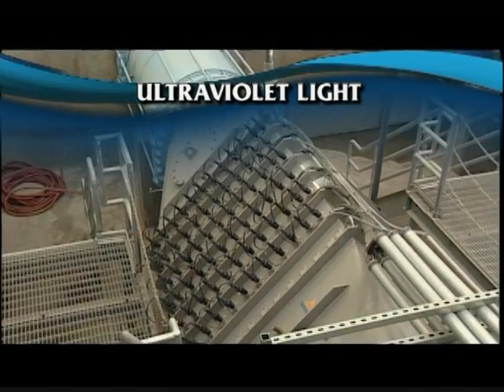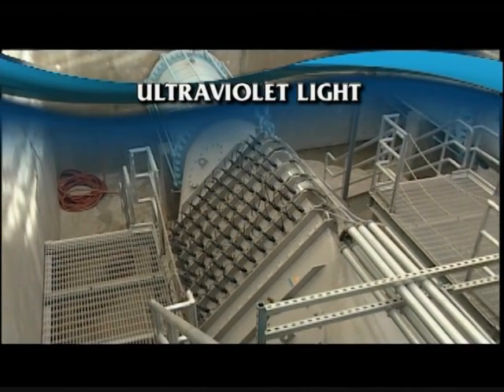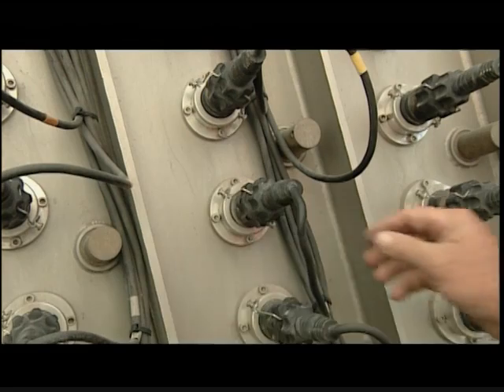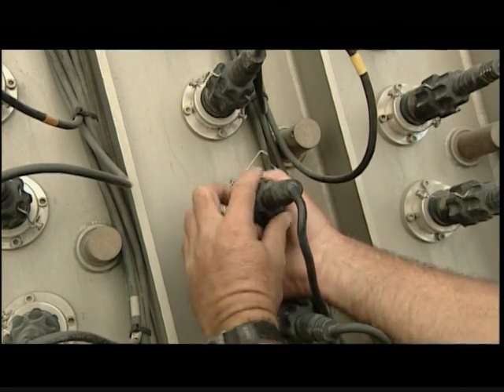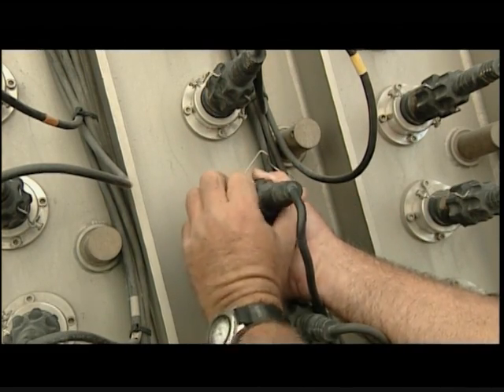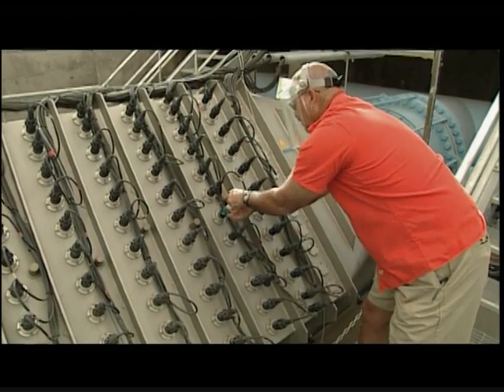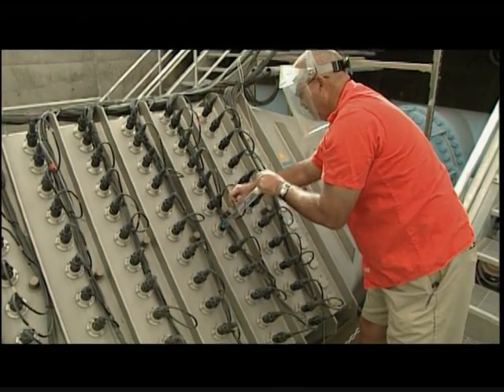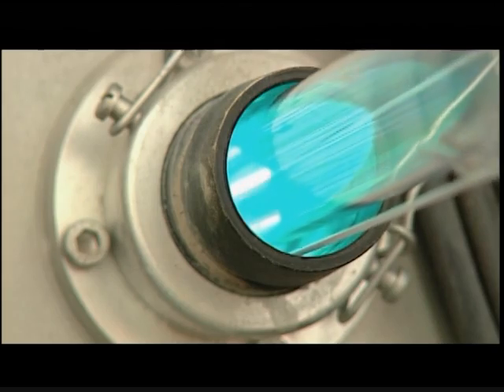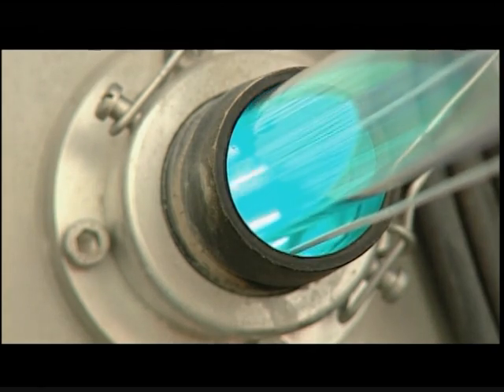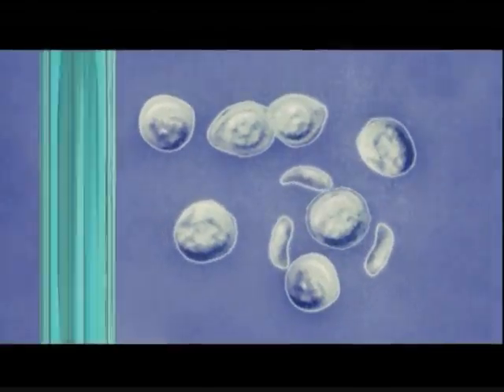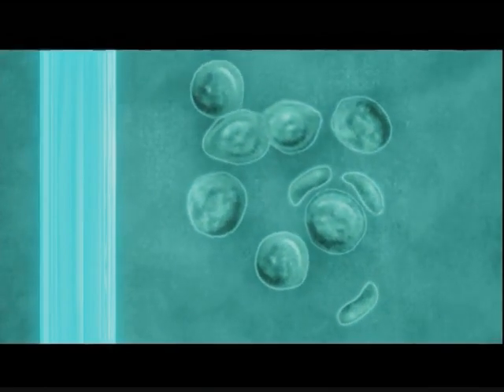Ultraviolet light, or UV, is the newest of the generally accepted disinfection strategies. UV inactivates microorganisms by irradiating them with ultraviolet light, thus disrupting the metabolic activity and reproductive process of the organism, rendering them inactive or incapable of reproduction. Particulate matter, or turbidity, interferes with UV light, thus lowering the amount available for inactivating pathogens. Therefore, UV is usually recommended for use after water has been filtered.